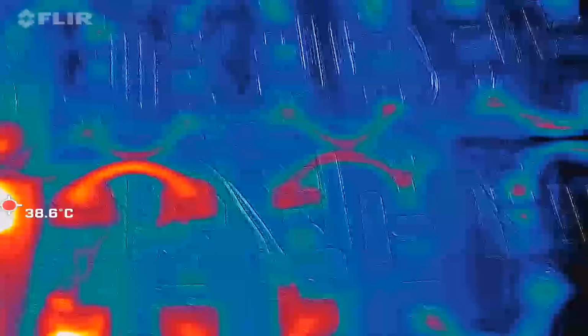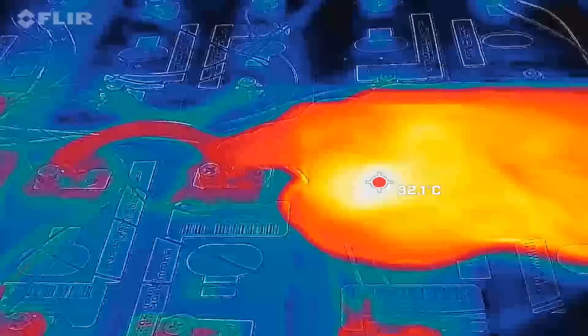Look at this, this is interesting. These bus bars here consist of 4 separate wires into one ring lug on each side. And this bus bar here consists of only 1 wire with the same ring lugs. Look at the temperature difference - this one is 25, which is not hot, and this one is like 23. So 2 degrees difference, and it looks like a lot, right?